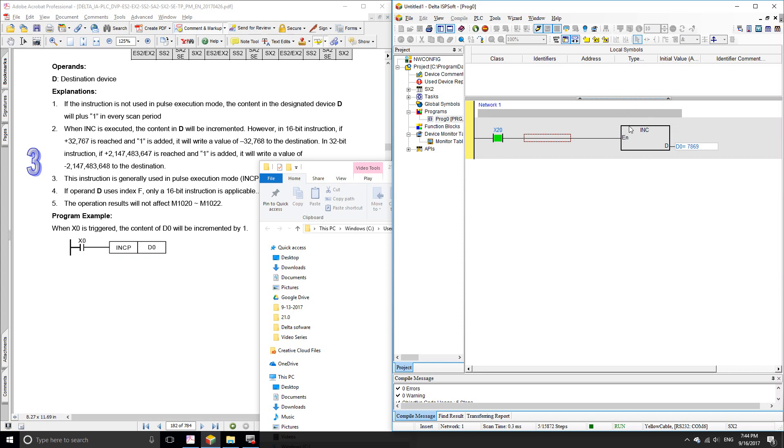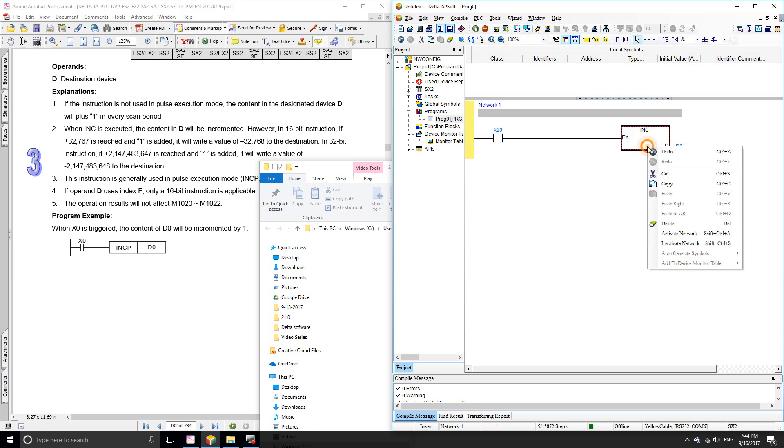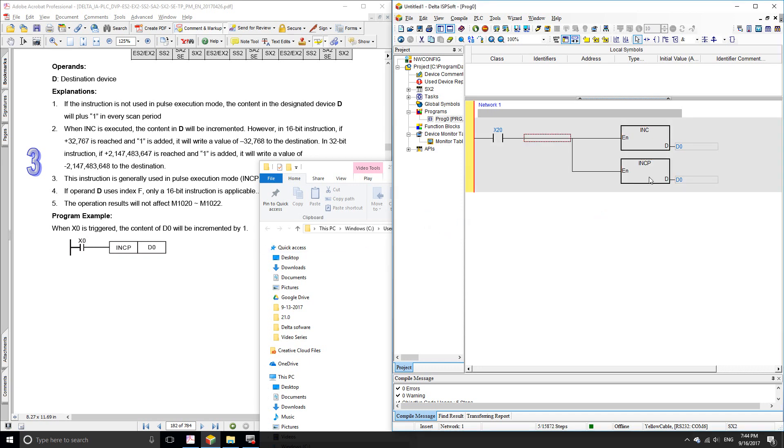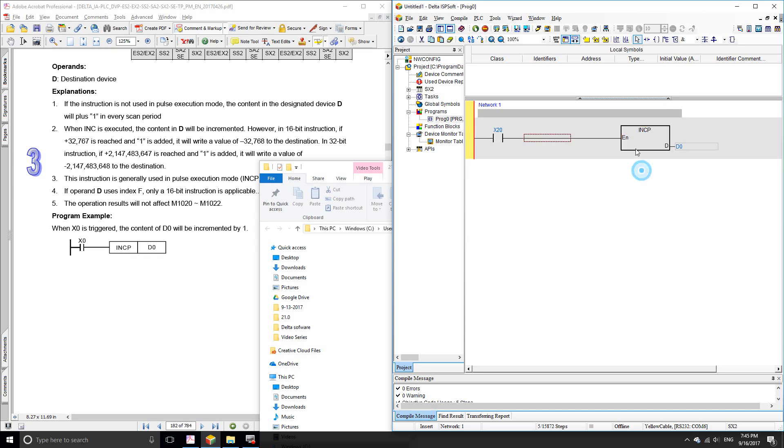It's being executed like hundreds or thousands of times per second. Now let's change this function and add the pulse option. Let me double-click it and I'm going to add at the end of the instruction the letter P. Hit OK. The new instruction is being generated underneath, so I'm going to delete this one. I'm going to compile it and load it to our PLC. The PLC goes to stop.